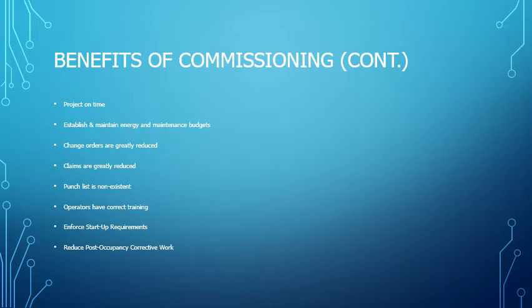Another benefit of commissioning is we want to make sure the project schedule is on time, and that we establish and maintain the energy and maintenance budget. Change orders are greatly reduced, and claims are also greatly reduced because more complaints mean more work to be done. So we want to make sure claims are minimized, the punch list is nonexistent, and the operator has correct training from the operation and manual documentation. We also want to enforce the startup requirements, and reduce post-occupancy corrective work, which is defect work.